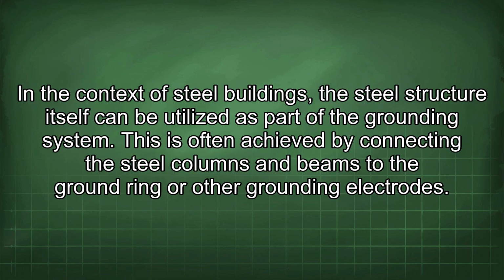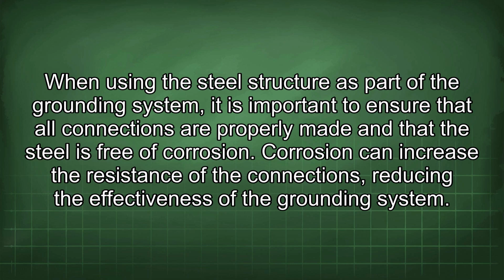In the context of steel buildings, the steel structure itself can be utilized as part of the grounding system. This is often achieved by connecting the steel columns and beams to the ground ring or other grounding electrodes. When using the steel structure as part of the grounding system, it is important to ensure that all connections are properly made and that the steel is free of corrosion. Corrosion can increase the resistance of the connections, reducing the effectiveness of the grounding system.